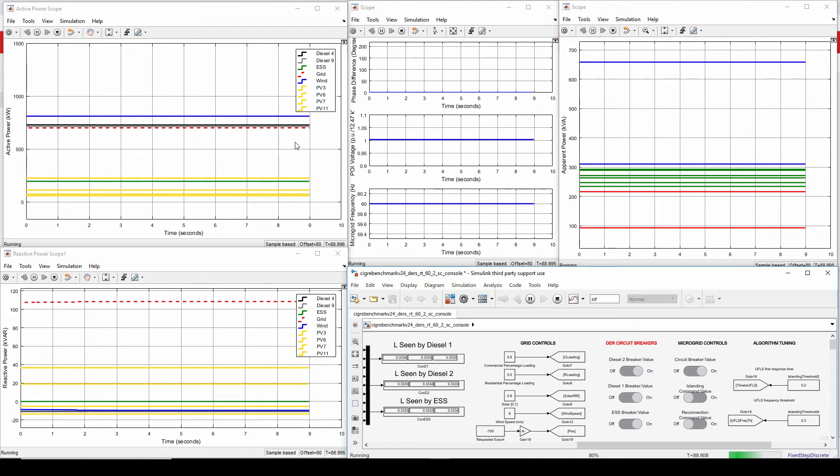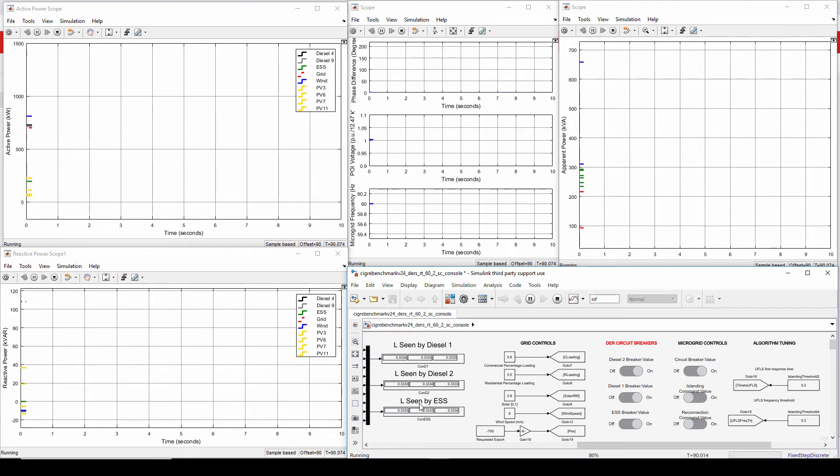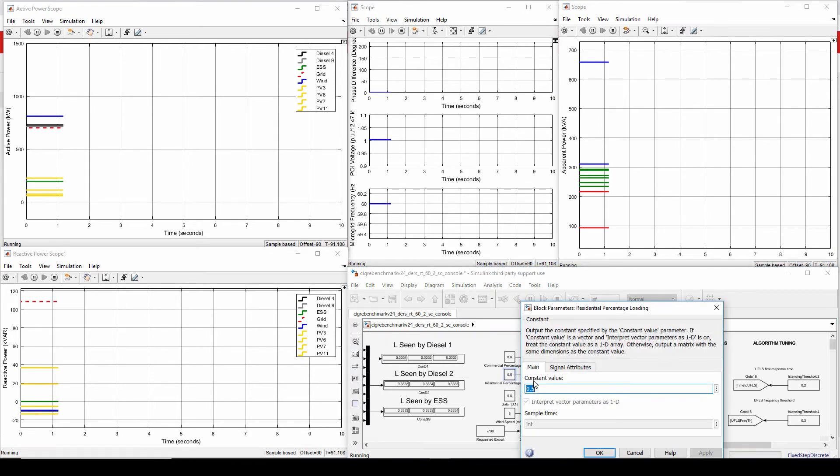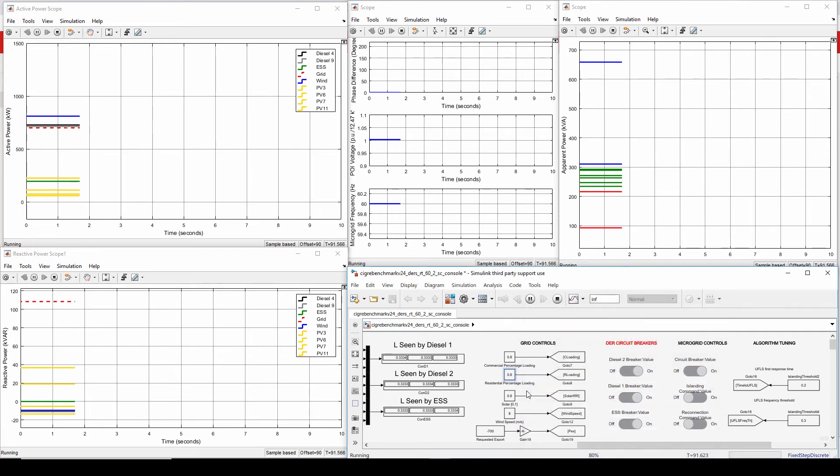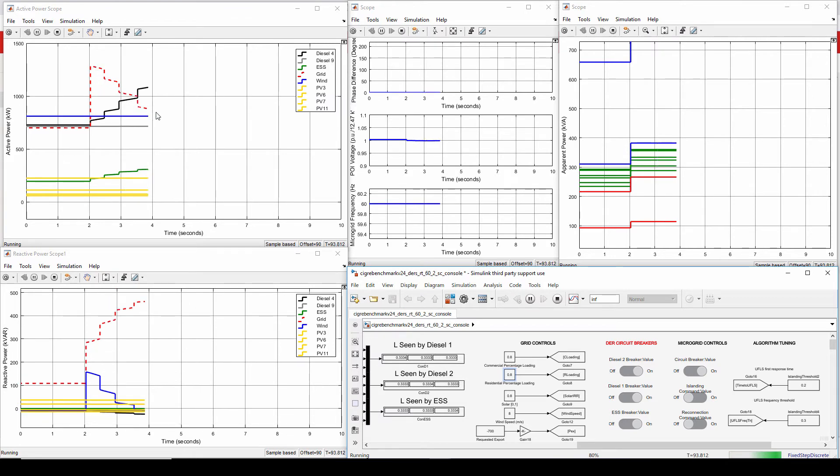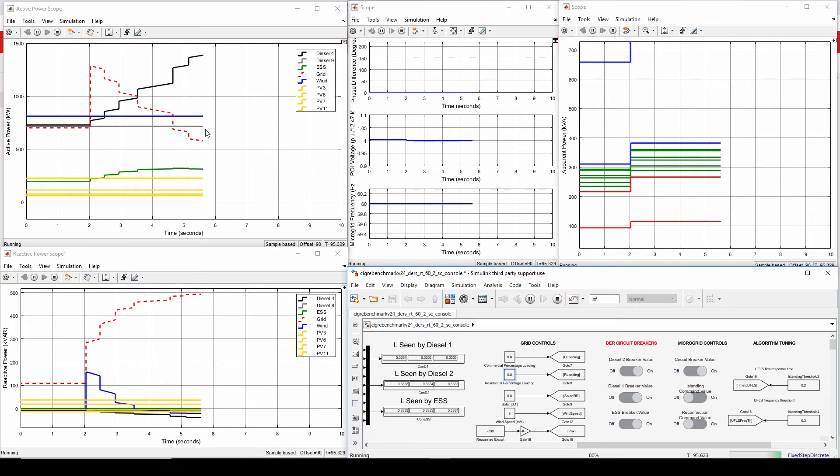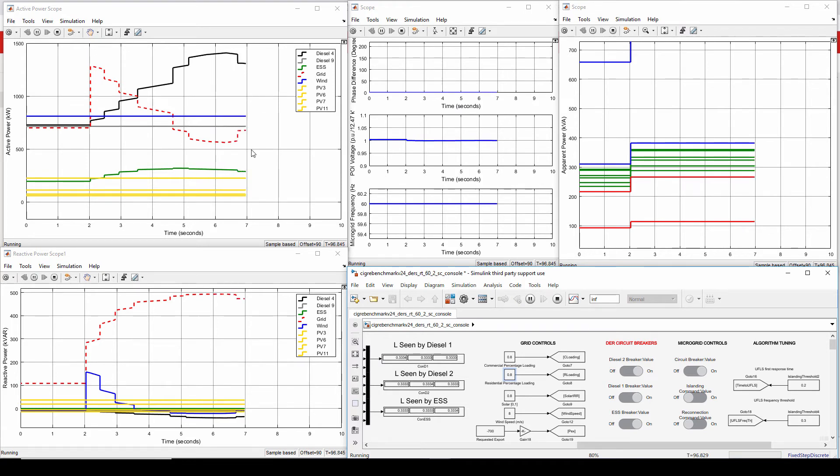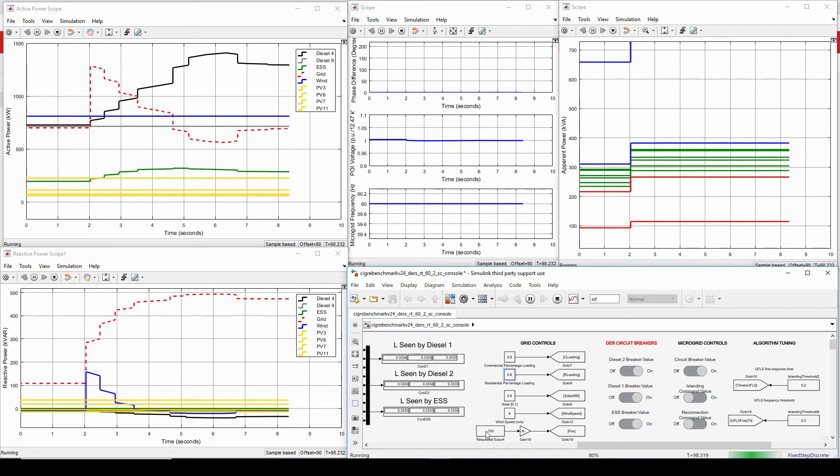So now I have connected diesel 2. The L matrices got updated. Now I'm going to change the residential load in grid-connected mode to 80%. So these guys stepped up and again the grid picked up the load and now it is again being regulated back. Diesel 2 is already generating its maximum power, and the ESS and diesel are trying to regulate the POI back to 700 kilowatts.